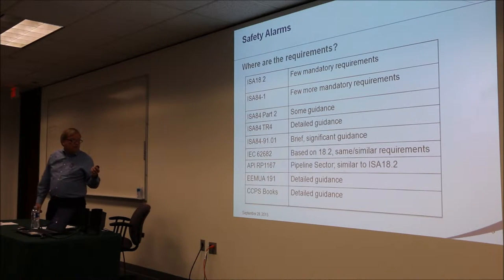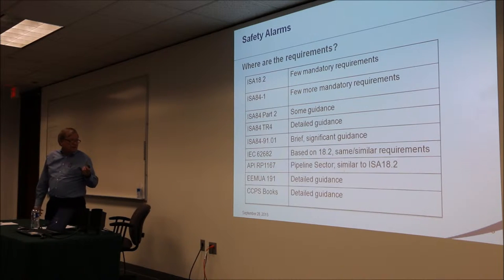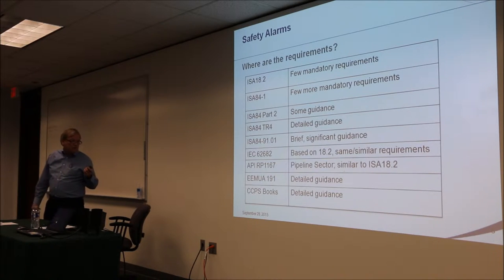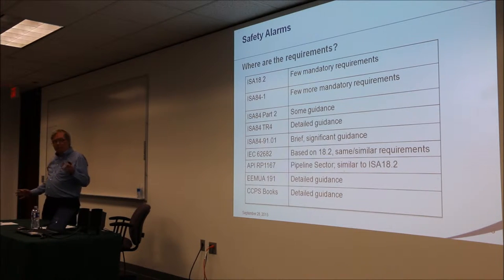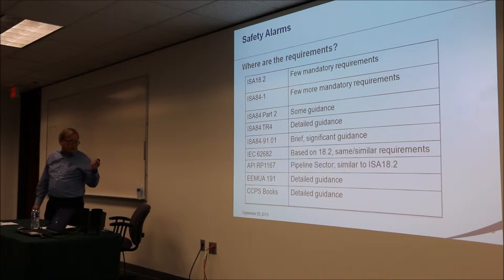Where are the requirements? In 18.2 there are a few shall statements, but not a whole lot. There are a few more in the main standard ISA 84, but in my opinion there are definitely some aspects that can be missed. Part 2 has some guidance, and TR-4 has very detailed guidance — probably the biggest resource for requirements is ISA 84 TR-4.